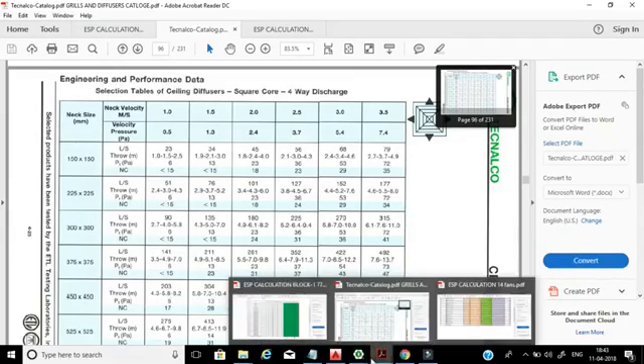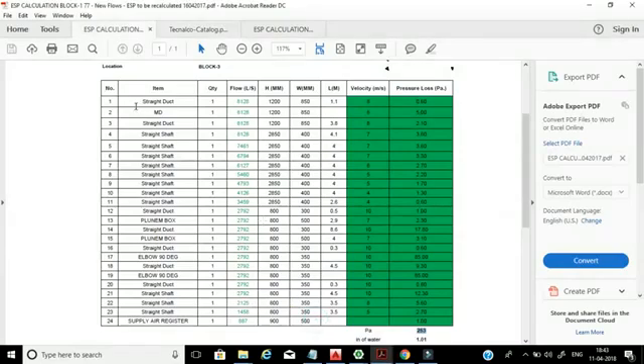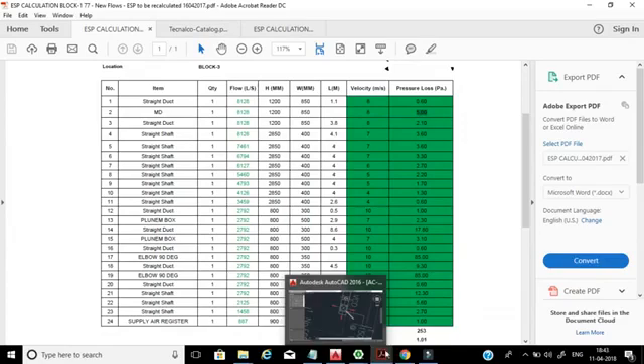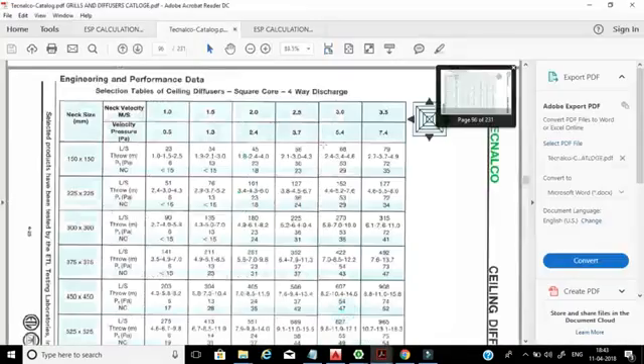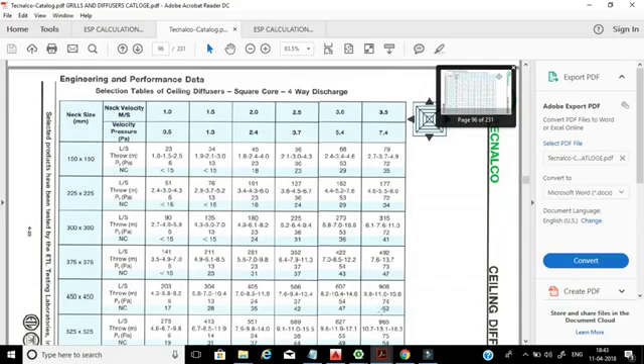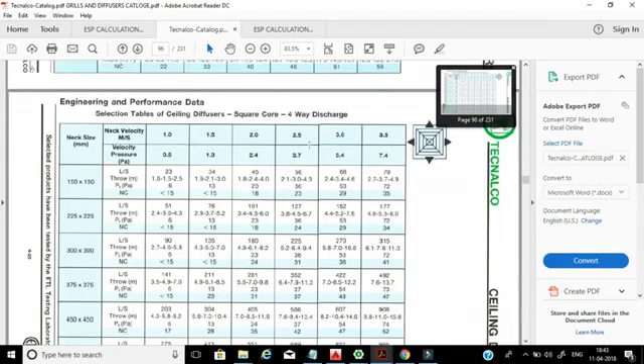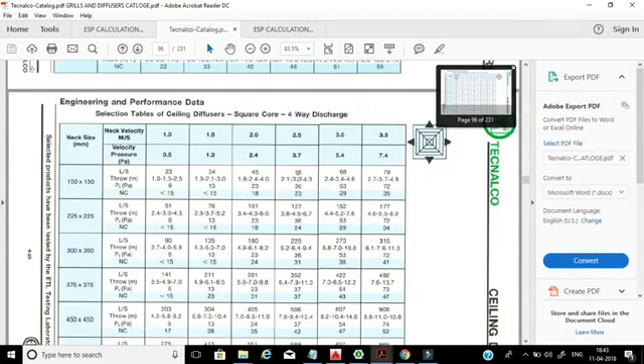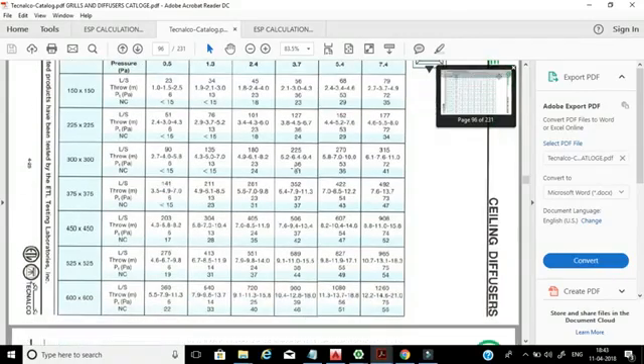For the supply air diffuser, you can mention the velocity pressure directly — 3.7 Pascal — in the Excel sheet pressure loss column. For the VCD, mention the flow rate, neck size, and Pascal value from the catalog. While you are submitting the ESP, you need to print out this catalog page and highlight the relevant row, so the person reviewing it will understand very quickly that the ESP value was taken from this reference.